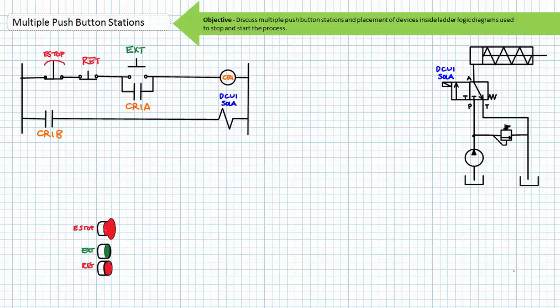Notice that while in its natural deactivated closed state, the maintained contact e-stop in no way affects functionality of the system. When an operator presses and releases extend, the cylinder would extend completely to the limits of travel and remain extended. When an operator presses and releases retract, the cylinder would retract, ready to initiate another extend and retract cycle. If, however, an operator were to observe an unsafe scenario, by hitting the maintained e-stop the cylinder would retract and the system would be disabled. Due to the maintained rather than momentary nature of the e-stop, the system will remain disabled until the e-stop is reset. The extend button will not energize the coil of CR1 and DCV1 solenoid will not energize despite repeated attempts. Only after the e-stop has been reset and returned to the closed position can the system extend the cylinder again.